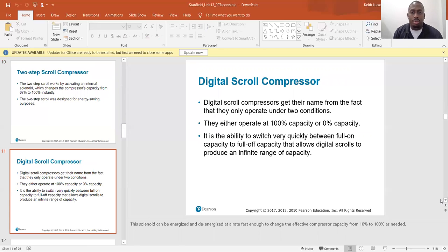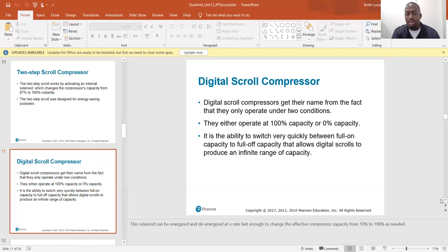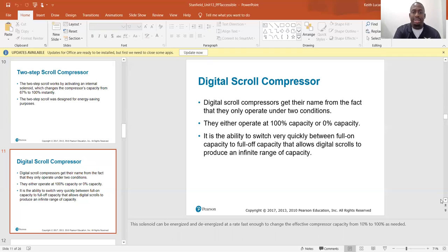Digital scroll compressors get their name from the fact that they only operate under two conditions: either 100 percent capacity or zero percent capacity. The ability to switch very quickly between full-on and full-off capacity is what allows digital scrolls to produce an infinite range of effective capacity.